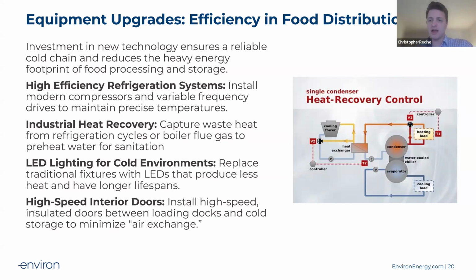That's typically a major opportunity for this industry. You have a lot of waste heat going out the door, whether from sanitation or the boiler itself. That could potentially be reused to preheat water used for other applications like process or sanitation. It doesn't have to mix waste streams - it's simply a water-to-water heat exchanger that isn't contacting the two water streams. It's a real opportunity to capture a ton of heat and reuse it instead of dumping it down the drain.